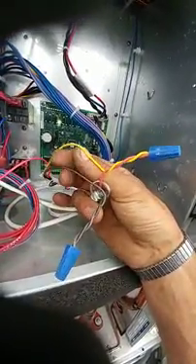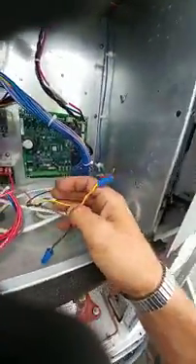These wires are for our CO2 sensor. From the CO2, it just has a signal, a common, and a power. We ran these two wires over here. You have to power the CO2 down there, so we have 24 volts coming off a constant 24V — you can pull 24V from pretty much wherever you want, transformer or whatever, but this is the closest location. Common runs to your common block — any common will do. Then these two wires go down to our economizer board: red and black, hitting our two to ten volts DC. There are six wires coming off the CO2 sensors — we did not use the normally-open contact relay, we used the two to ten because of the economizer board thermostats.